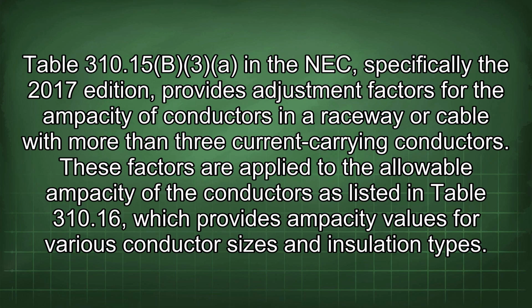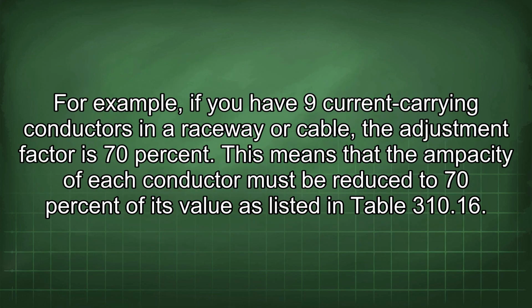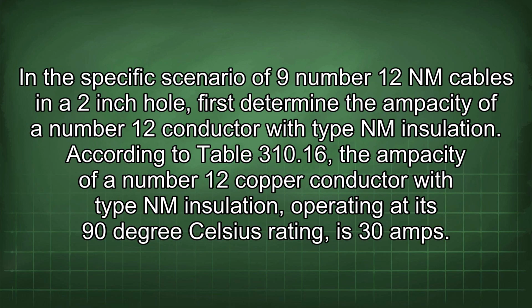These factors are applied to the allowable ampacity of the conductors as listed in Table 310.16, which provides ampacity values for various conductor sizes and insulation types. For example, if you have 9 current-carrying conductors in a raceway or cable, the adjustment factor is 70%. This means that the ampacity of each conductor must be reduced to 70% of its value as listed in Table 310.16.